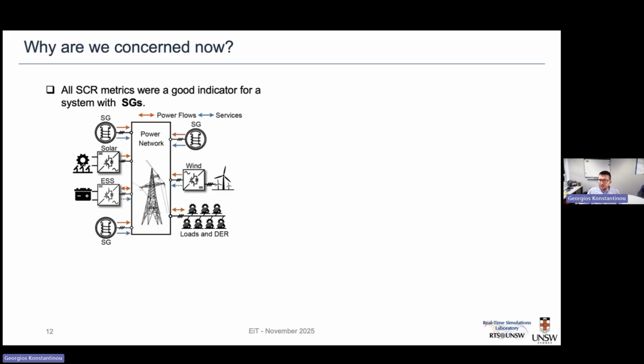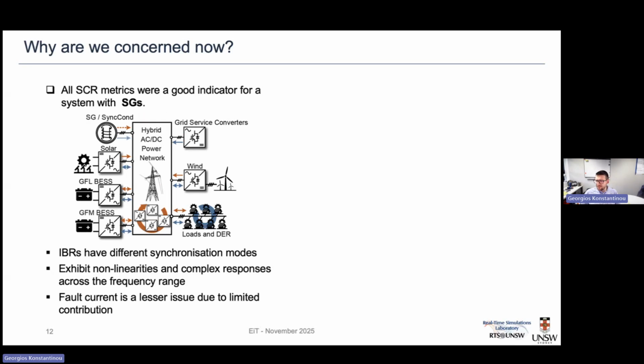These are very good indicators when we have a system with a lot of synchronous generation, and many systems still maintain a lot of synchronous generators. But in networks transitioning to more renewables, we find that a lot of generation no longer comes from synchronous generation, it comes from inverters, and this adds complexity to the analysis and takes away from the fundamental definitions we've used for a long time.